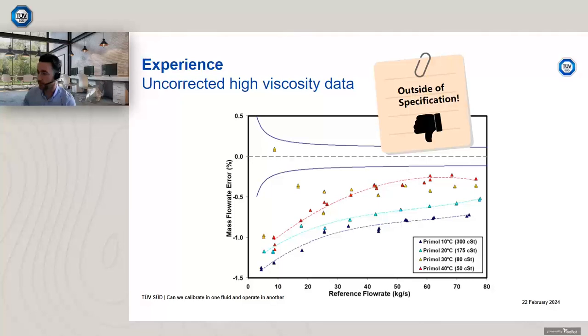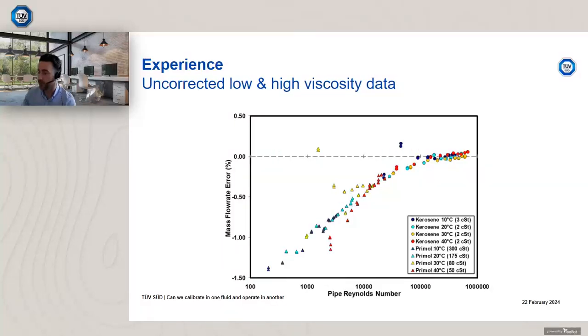So the meter's outside the specification, and you can see that there is certainly potentially a trend, but what if we plot that data with respect to Reynolds number? So now the same data as before. I have both the kerosene and that higher viscosity Primol data, plotting it all on the one chart, but this time with respect to pipe Reynolds number, as opposed to Coriolis tube temperature. This is the pipe, so nominal 6-inch device.